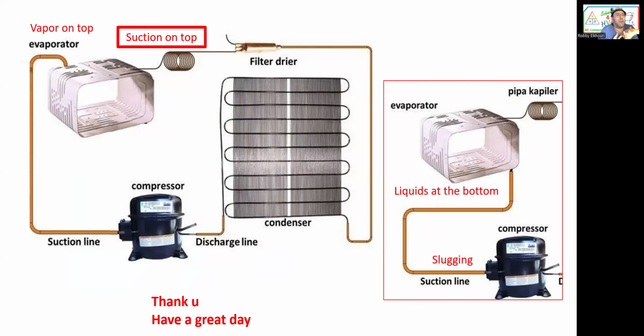There we go. Suction on top, people, always. All righty. Discharge, correct, on top. Vapor on the top, correct. Vapor turns to liquid, correct. Liquid at the bottom, correct. Goes to filter dryer, correct. Capillary tube metering device, correct. And on top, correct. But then it should be on top. Vapor goes back on top, because the guy had it the other way. Well, that was the compressor slugging. Liquid at the bottom caused the compressor to slug. It is amazing how many wrong things I see online, people.